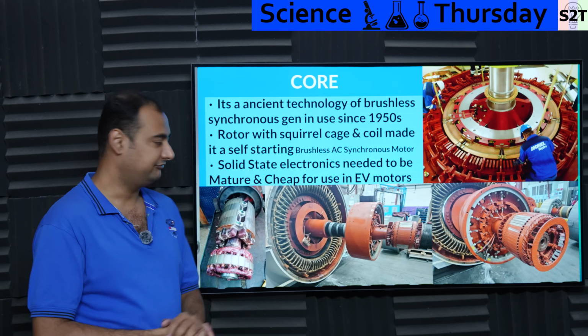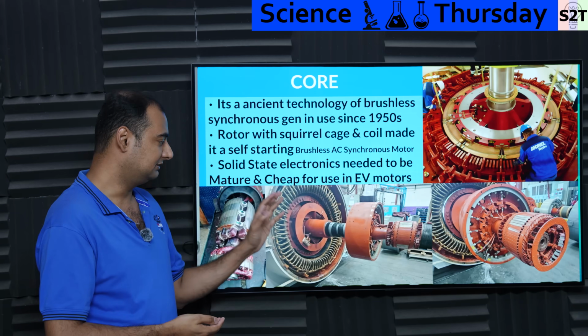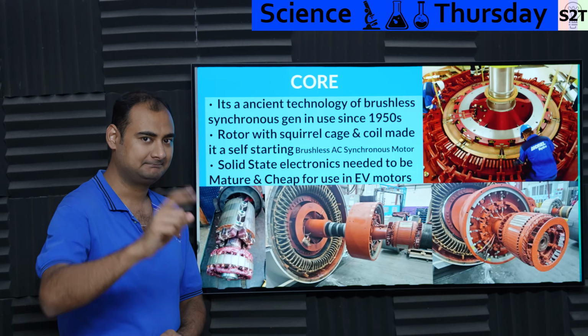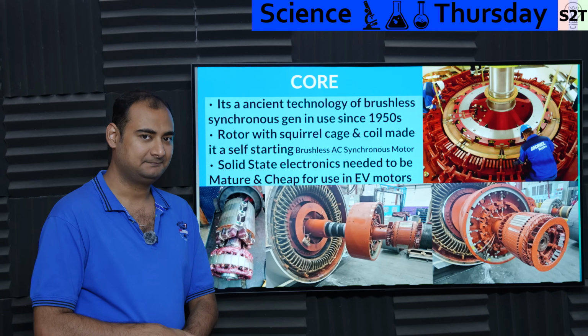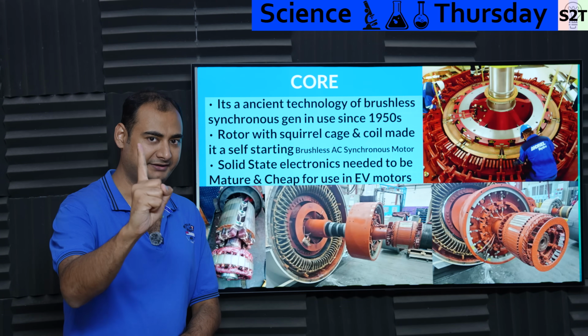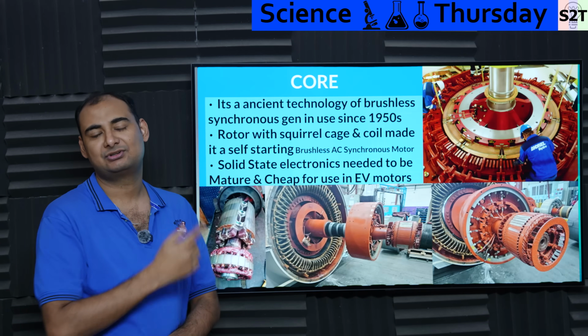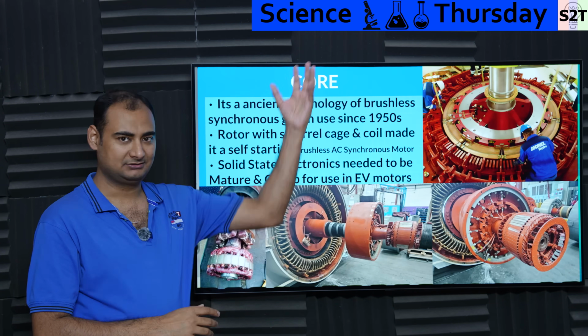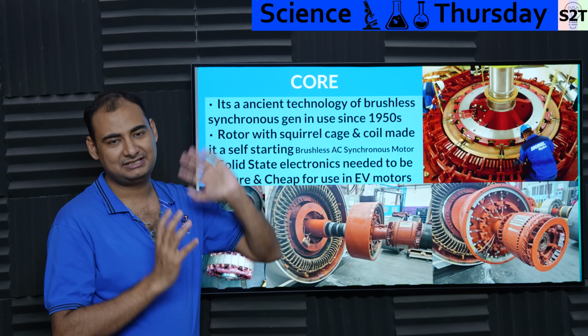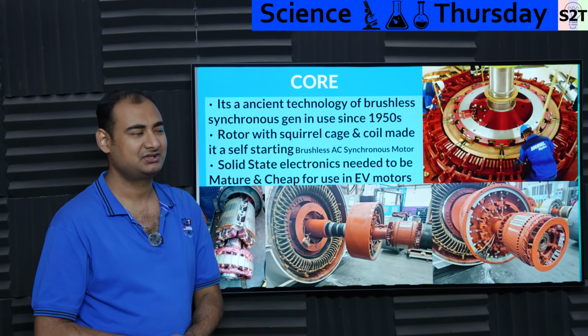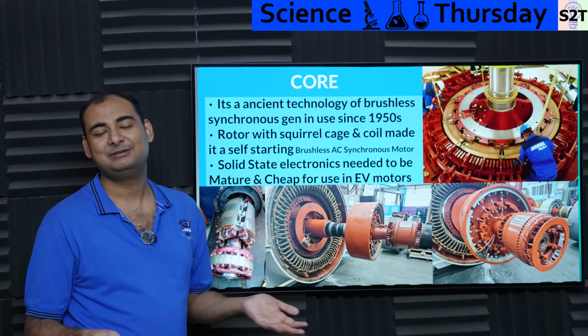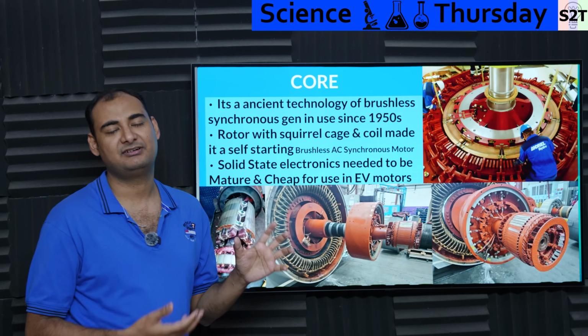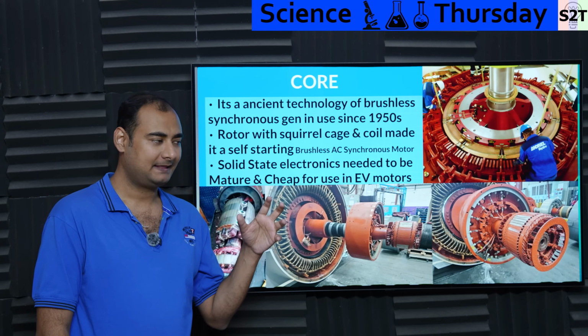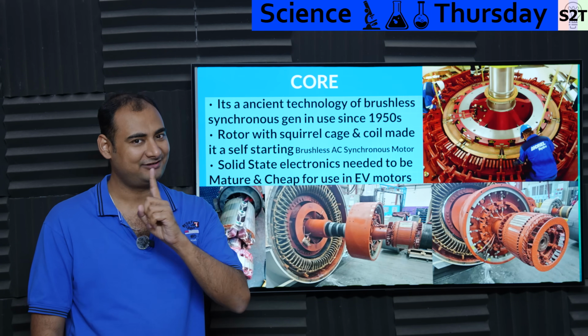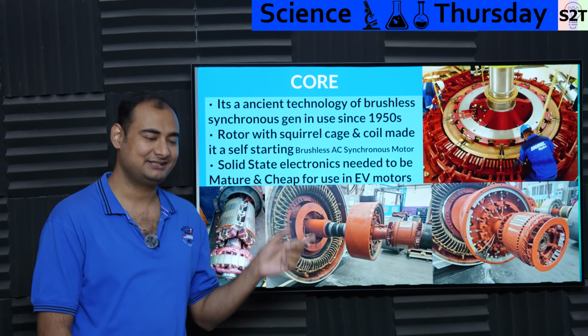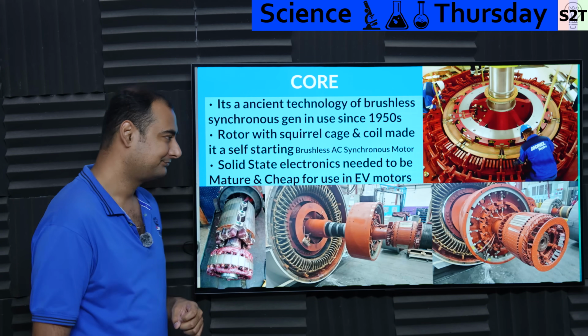However, somebody was like, hey, we want this motor. Why? This puppy can run at a power factor of 1. Let that sink in. Power factor 1. If you look at a transformer near you, the pole transformer, house transformer, whatever, they generally say kVA, kilovolt amps. Why volt amp? Simply because with, let's say, 500 kilovolt amps, you can get 500 kilowatts out of it, but the power factor has to be 1. If the power factor is 0.7, you lose 30% of the capacity.